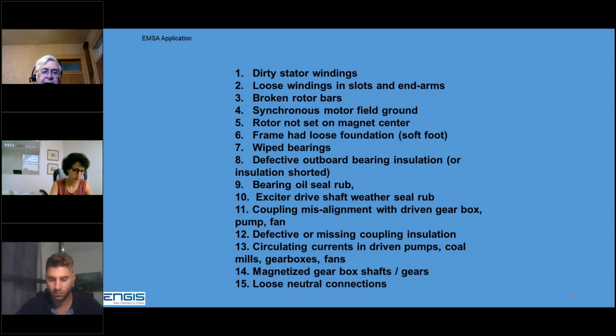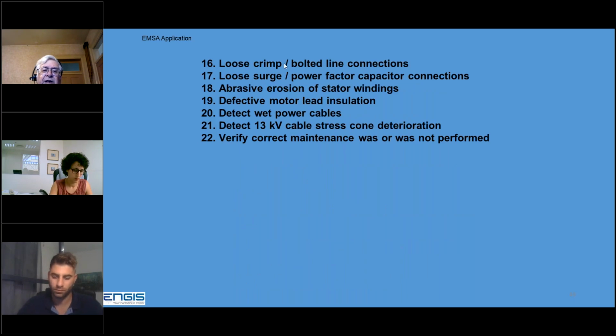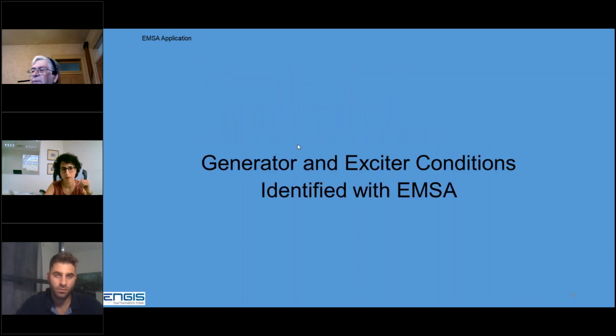And loose neutral connections. Loose connections on the line side, power factor correction capacitors, abrasion on the stator windings where sand has eaten away the insulation on the windings. Defective motor lead insulation. We found several people that put in leads that don't have enough insulation on them. Wet power cables, I showed you an example of that. Stress cone problems, and you can verify that the maintenance you performed was or was not good.